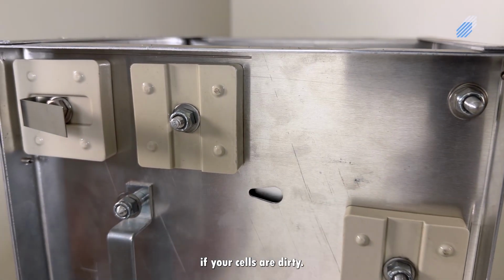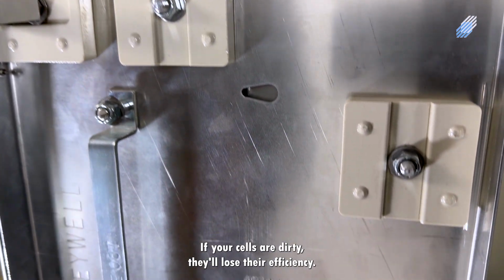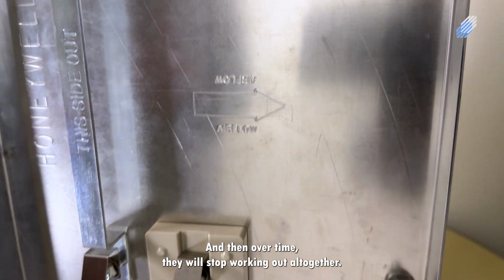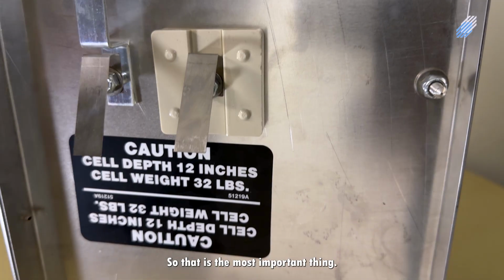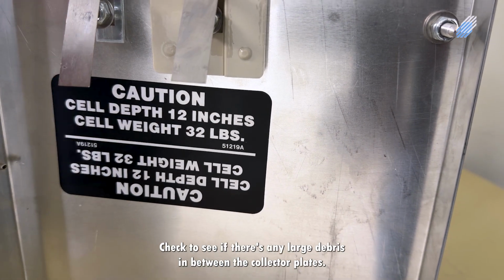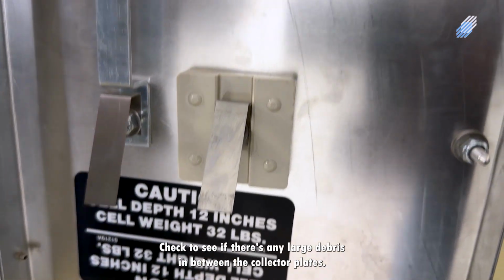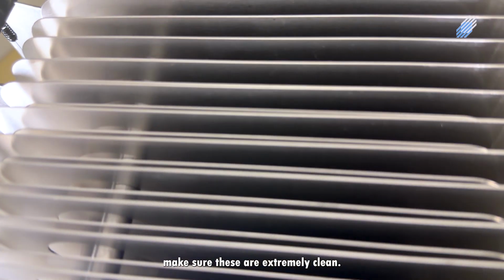The last thing to see, and this is the most important thing that we tell customers, is to check if your cells are dirty. If your cells are dirty, they'll lose their efficiency, and then over time they will stop working altogether. So that is the most important thing. Check to see if there's any large debris in between the collector plates. Make sure these are extremely clean.